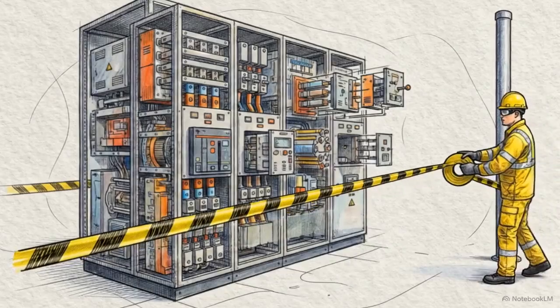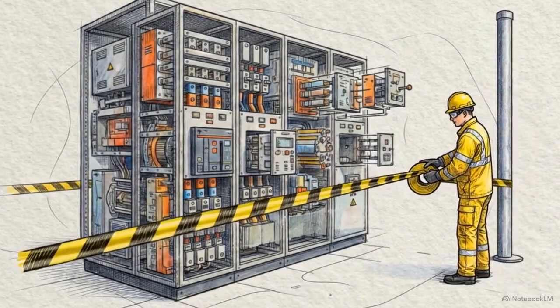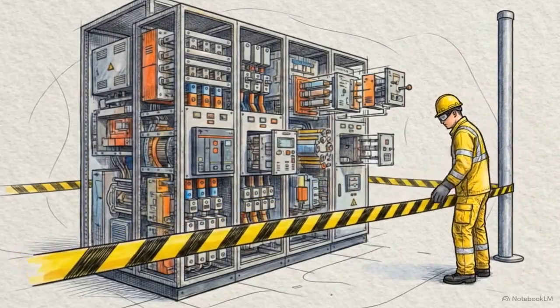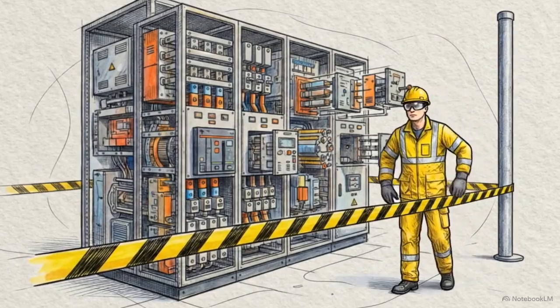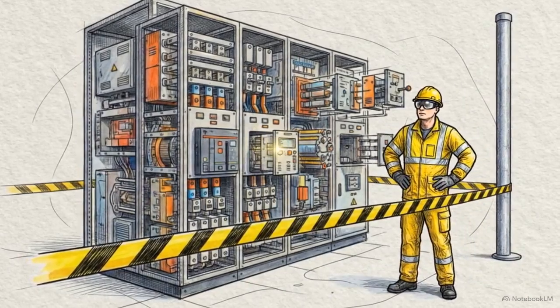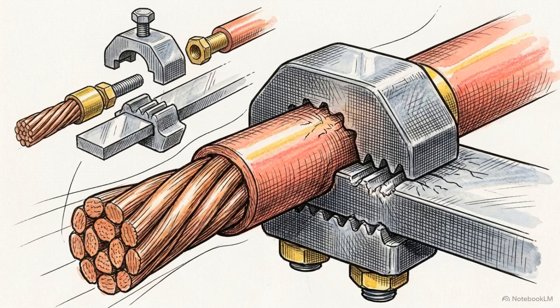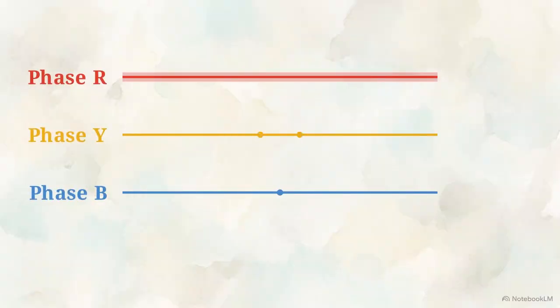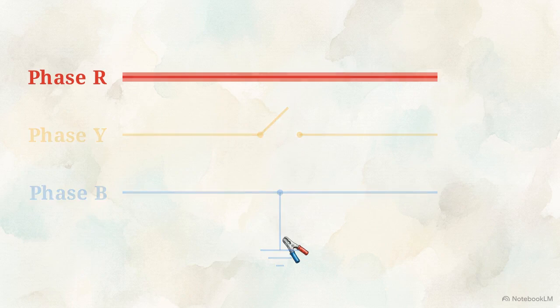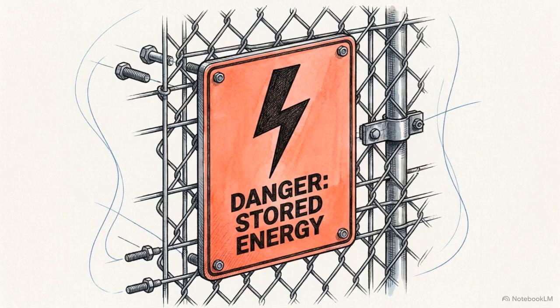The baseline begins with the physical application of lockout and tagout protocols. Technicians barricade the test area and independently verify the total absence of voltage. Following isolation, temporary earths are installed wherever required by the specific test schematic. Technicians must ensure that all non-test phases remain either physically open or grounded, completely neutralizing parallel phase hazards. Finally, safe discharge protocols are mandatory.